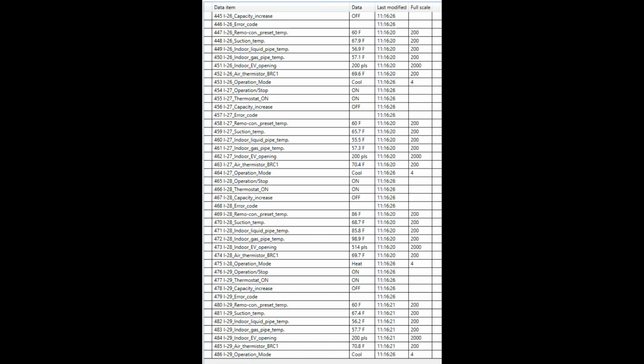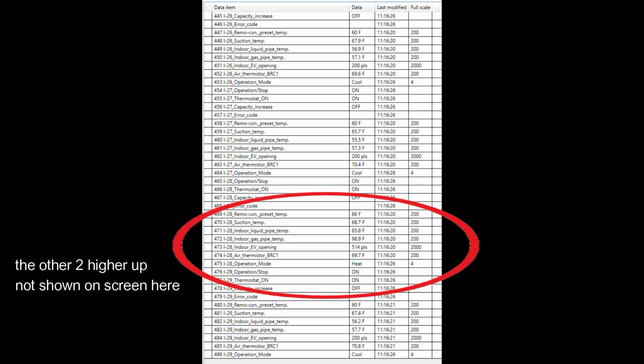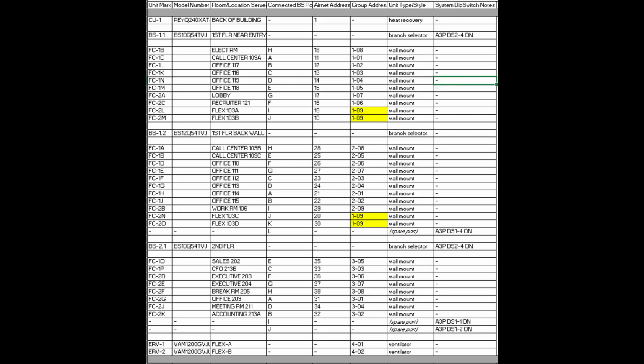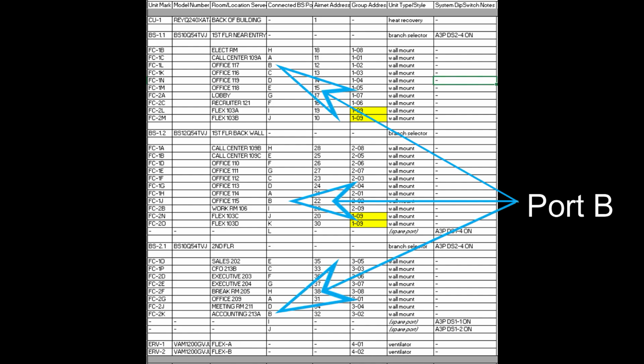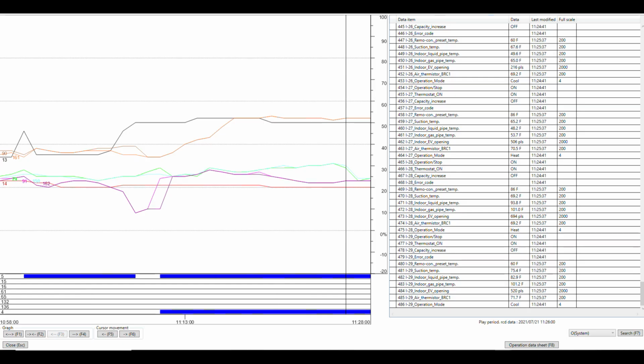The good news is that our first set of ports were all wired correctly, and you can see here that we have hot gas going to all three of the indoor units that are in heat. So now it's time to switch over the second set of ports of each box over to heat. So this time it'll be port B of each of our boxes. Again, a 5-minute wait period for the indoor units to equalize, receive hot gas, and open the EEV at the indoor unit to heat the space.